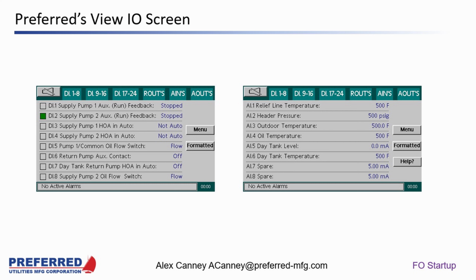Otherwise, you can chase your tail for a long time looking for a loose wire in a terminal. From a field standpoint, my standard for doing a startup and even service is to check all the terminations and make sure they're snug, because who knows what happens. With these European style terminal blocks, you can stick the wire in, tighten it down, and it'll look like it's in the cage, but it's not. You give it a pull test and the wire comes right out. So every wire should get a pull test after you've tightened it down.